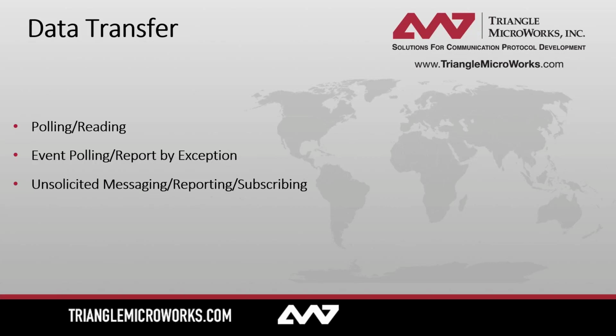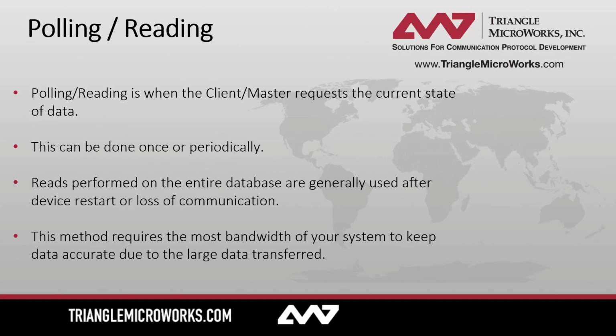So now let's talk about data transfer. We have grouped different methods of data transfers into 3 different groups. While these methods may not be 100% identical protocol to protocol, we can draw some comparisons between them. Polling or reading is when a client requests the current state of data. This can be done either once or periodically, and reads are performed on an entire database, generally after the device has been restarted or there's been a loss of communication, to make sure that you can quickly get back on track and make sure that the client or master's database is up to date again. This method requires the most bandwidth of your system to keep data accurate due to the large data that's being transferred.